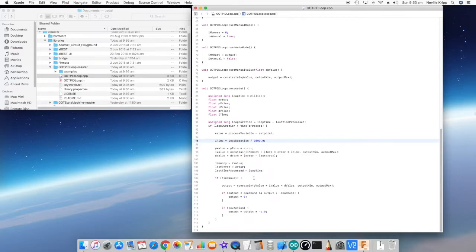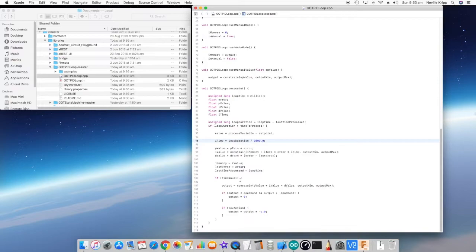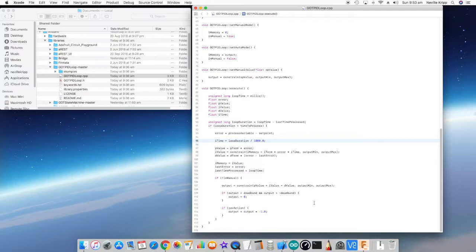If it is in manual, we don't do anything further because we're specifying the output manually. However, if it's not in manual, then we assume that the loop is in auto and we actually calculate the output. We add the p value, the i value, and the d value, and we constrain it within the output limits. Now if we've got some dead band applied to the actual output, then we check to see whether it's within the ranges of that dead band. If it is, we set it to zero.